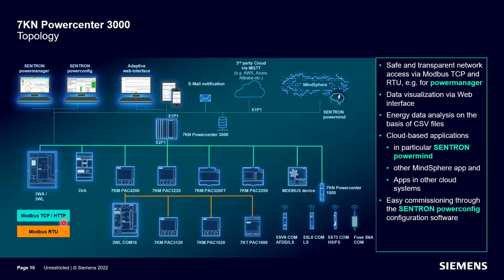For example, there's a specific device, 4200, which can connect 16 or 17 RS485 devices to it, collecting the data through this gateway. So both protocols, Modbus TCP/IP and Modbus RTU, can be connected through these devices to integrate with the IoT controller.